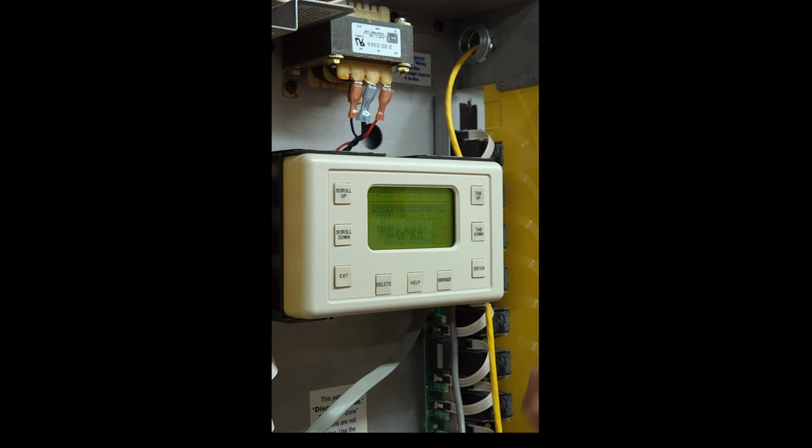Hit enter. If you press the front button of that switch or that black button, it tells you what the address for this switch is. Go ahead. What does it say? It says address is 46, and then it's got a serial number. Exactly. So you see, we already addressed it. Now, for all intents and purposes, 46 is one of the switches shown in this panel. So hit exit back to user menu so I can show you in the program switch. It's going to show you 46. Go back to the main menu.